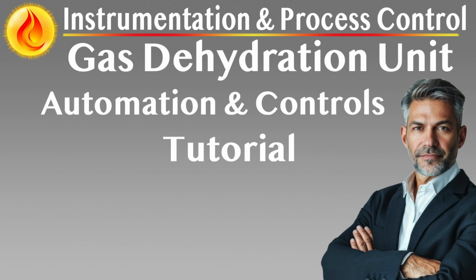Control objectives and functions. Gas side control parameters. Inlet gas flow control. In systems without upstream compressor regulation, inlet gas flow is indirectly managed via downstream pressure control valve. Flow measurement using a differential pressure transmitter, DP cell, or ultrasonic meter upstream of the control valve ensures regulated throughput. Contactor pressure monitoring. Pressure transmitter, PT, at the gas outlet monitors internal contactor pressure.